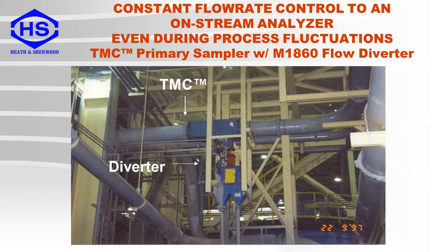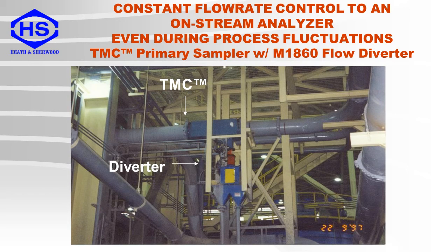This is an example of a TMC sampler with a diverter. The diverter has two discharge pipes — one is for the reject and the other supplies a sample to an on-stream analyzer. The slurry level in the analyzer outlet section of the diverter can be controlled so that a constant flow of slurry can be maintained to the analyzer.